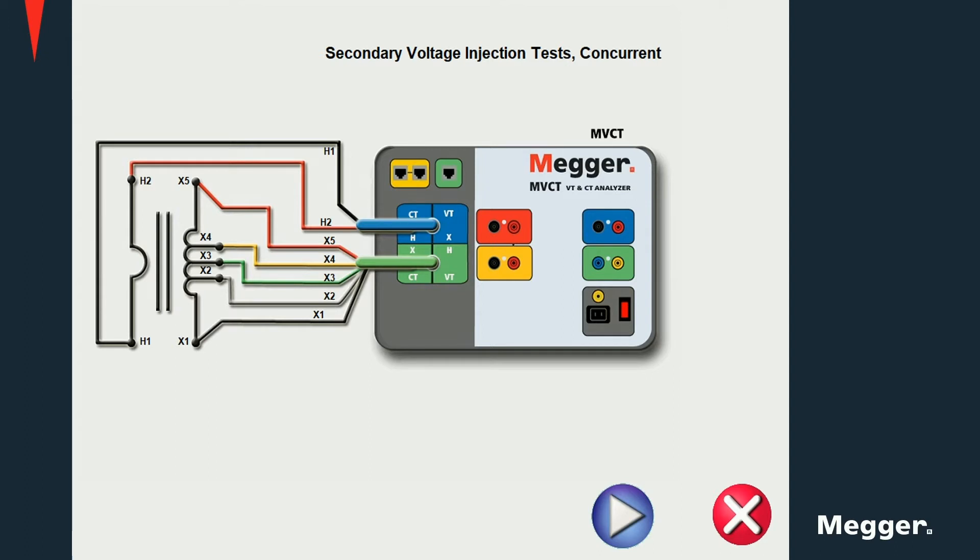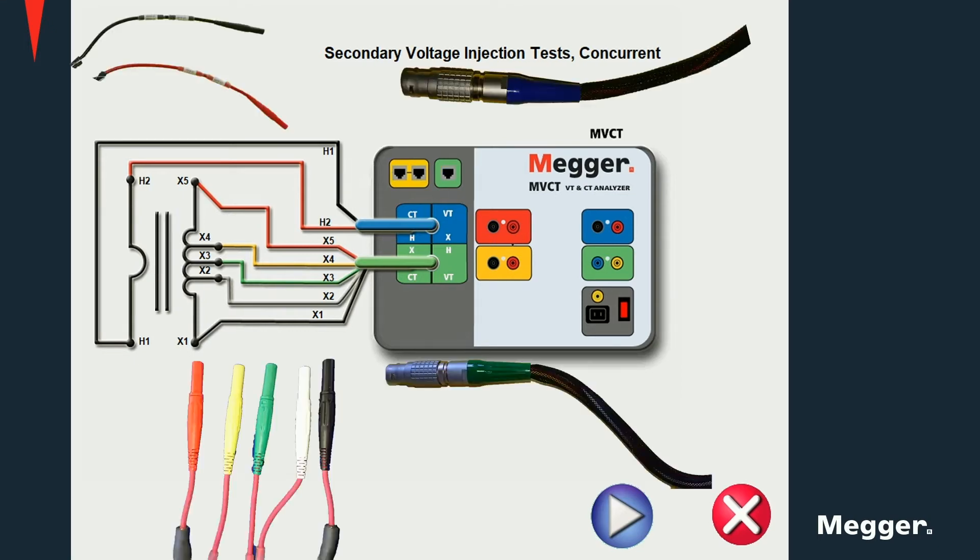It is important to remember that when testing with the MVCT, most tests can be performed without changing the connections. Tests like insulation, winding resistance, excitation, ratio, and demagnetization procedures are performed concurrently without having to change the connections. The color coding and markings make the connection diagrams very easy to follow. We can see them here both on the connectors from the primary and secondary cables on the MVCT, as well as for the connectors provided for the connections on the CT itself.